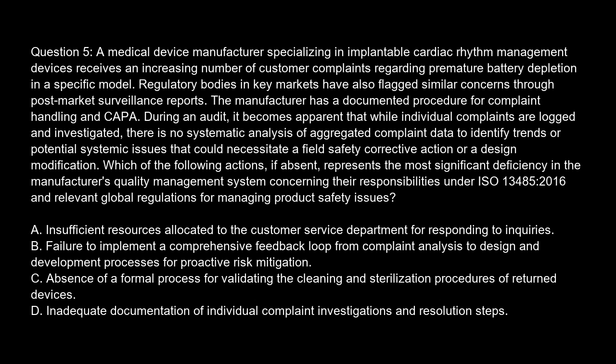During an audit, it becomes apparent that while individual complaints are logged and investigated, there is no systematic analysis of aggregated complaint data to identify trends or potential systemic issues that could necessitate a field safety corrective action or a design modification. Which of the following actions, if absent, represents the most significant deficiency in the manufacturer's quality management system concerning their responsibilities under ISO 13485:2016, and relevant global regulations for managing product safety issues?